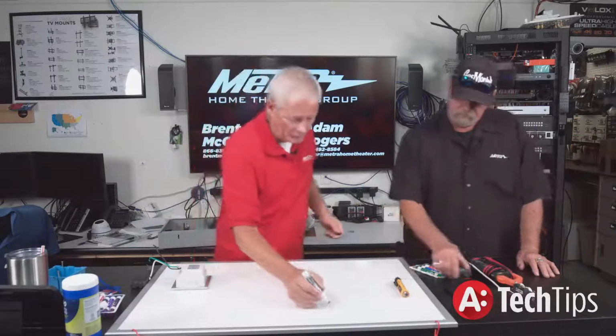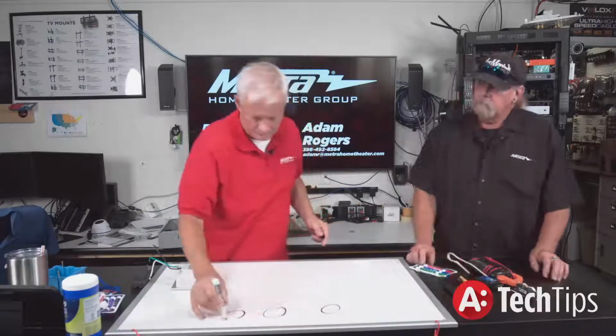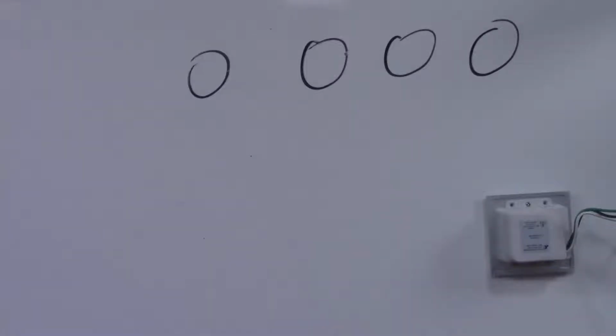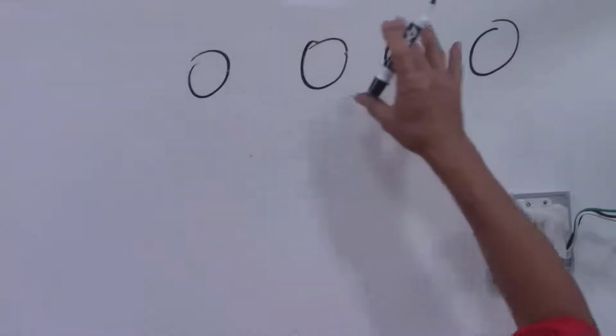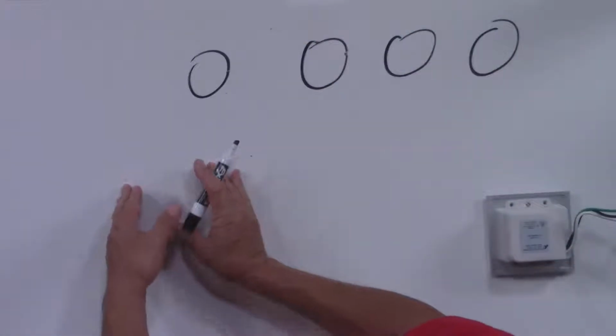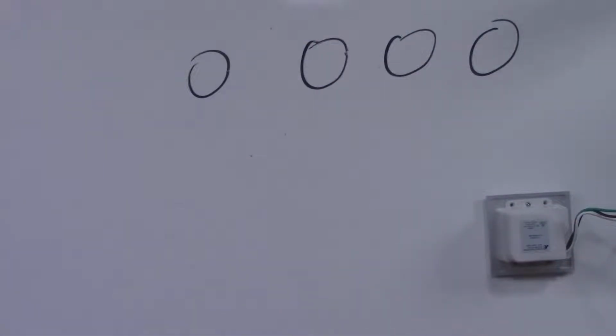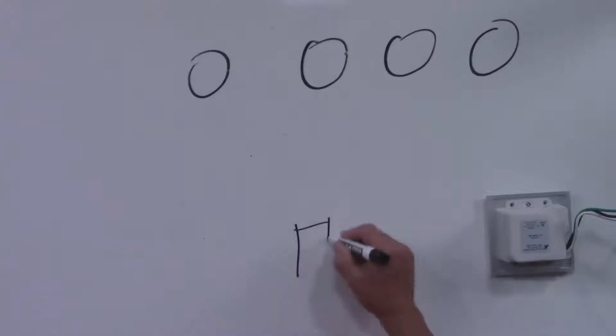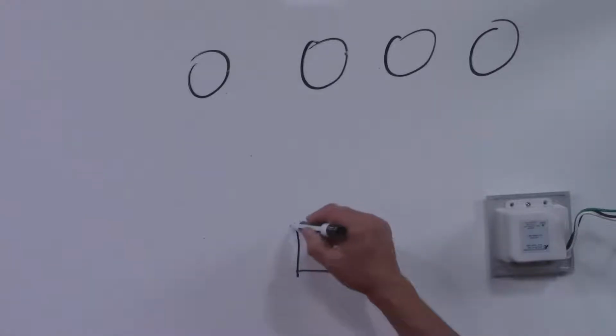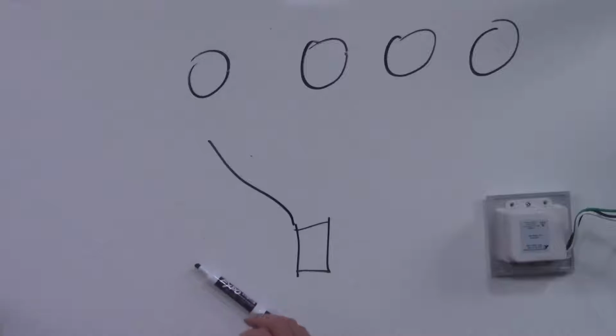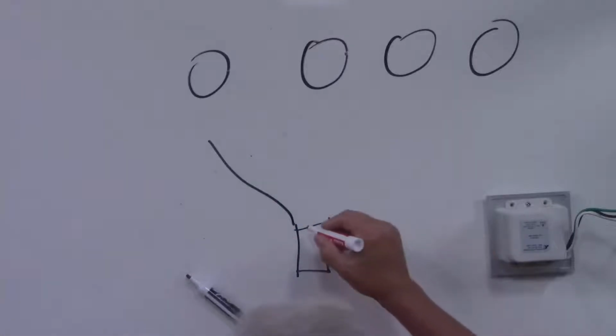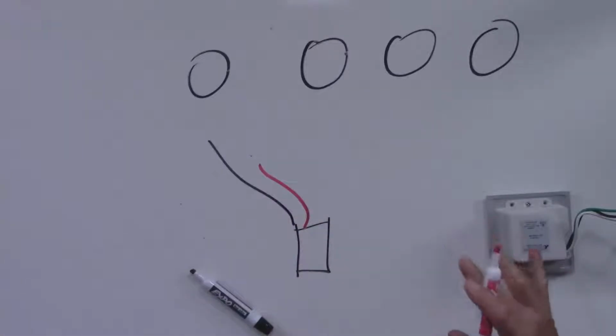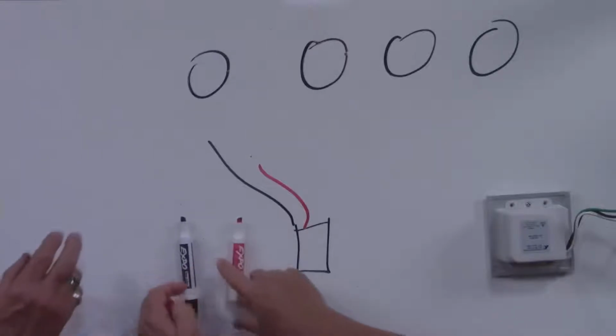Okay, let's say we're going to take four can lights. I need to feed all of them, and typically you have a couple of options. You can take all the pigtails to one point and put them in a junction box, which is paralleling, and it doesn't act like an audio amp. Or you could series them. So if I'm going to series them, I've got my junction box here with my white wire, a black wire, and another white wire, I'll use red for white. How do I series these correctly at each light?